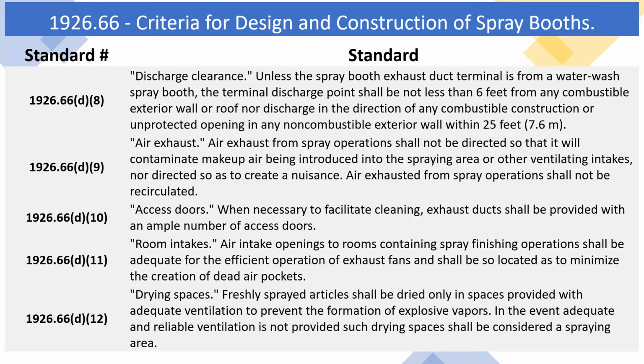1926.66(d)(8) Discharge clearance. Unless the spray booth exhaust duct terminal is from a water wash spray booth, the terminal discharge point shall be not less than 6 feet from any combustible exterior wall or roof, nor discharge in the direction of any combustible construction or unprotected opening in any non-combustible exterior wall within 25 feet (7.6 meters). 1926.66(d)(9) Air exhaust. Air exhaust from spray operations shall not be directed so that it will contaminate makeup air being introduced into the spraying area or other ventilating intakes, nor directed so as to create a nuisance. Air exhausted from spray operations shall not be recirculated.